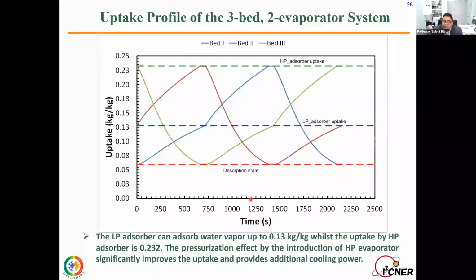So this is the uptake profile of bed 1, bed 2, and bed 3. Here you can see the low pressure adsorber can adsorb water vapor up to 0.13 kg per kg. That means if you have 1 kilogram of silica gel, it can adsorb 130 grams of moisture, while the uptake by the high pressure adsorber is 0.232. It's much better than the low pressure one because of the temperature and the pressure. The pressurization effect from the introduction of the high pressure evaporator significantly improves the uptake and provides additional cooling power. So we can get more cooling power from this high pressure adsorber bed. That is the novelty of this part.